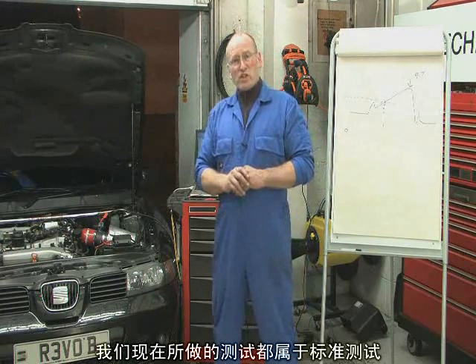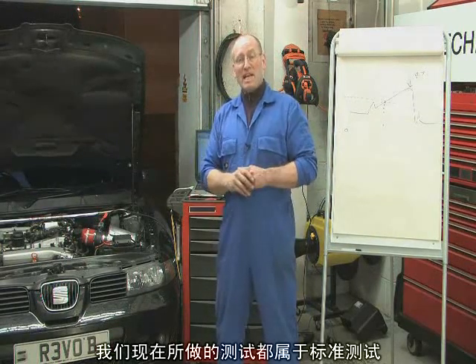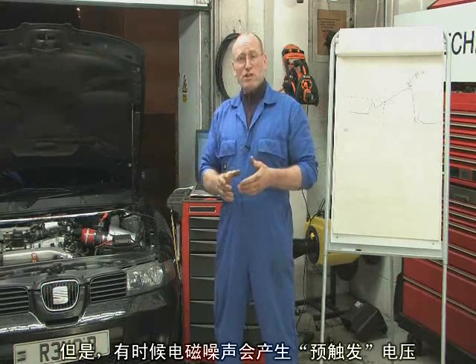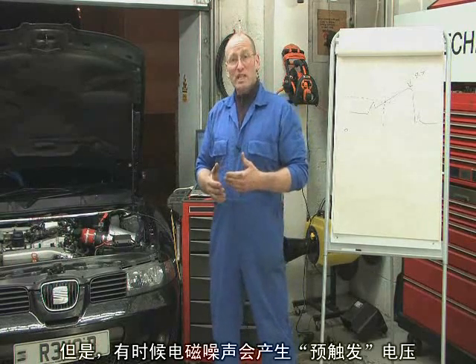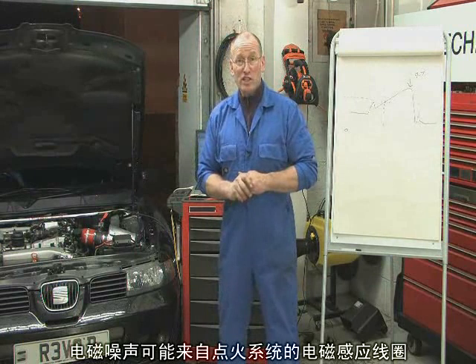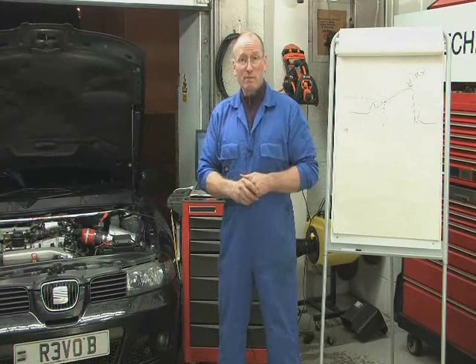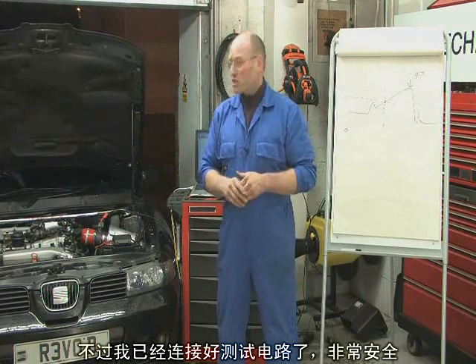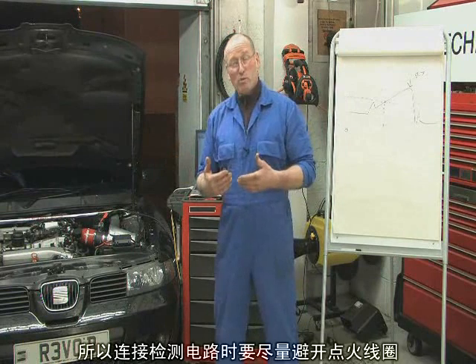What we've done is we've conducted a few sample tests. Sometimes you get what we call pre-triggering due to noise. Noise can be caused by ignition, induction interference, if you like, into the probe. So try and keep your probe well away from ignition.